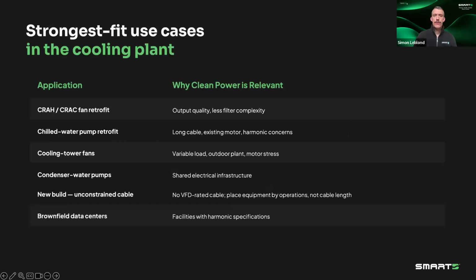I'll go quickly through this. You can use the Clean Power VFD anywhere where you have variable loads or even a constant torque load. It is a VFD like any other. From a usability perspective, where it really shines is any place where you would have that mitigation, you don't need it anymore, but also any place that would be constrained by cable length is suddenly something that you can reconsider.